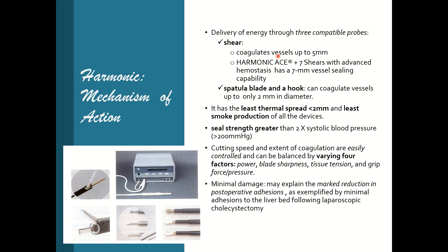With the shear, coagulation capability is up to 5 mm, but the newer Harmonic ACE goes up to 7 mm vessel sealing — roughly equivalent to a uterine artery. Initially the Harmonic was not advisable for coagulating the uterine artery, but now with the new Harmonic ACE+7 shears, even 7 mm vessels can be tackled. The spatula blade and hook can coagulate vessels only up to 2 mm in diameter. Thermal spread is less than 2 mm, and sealed vessels can withstand twice the systolic blood pressure, roughly 200 mmHg.